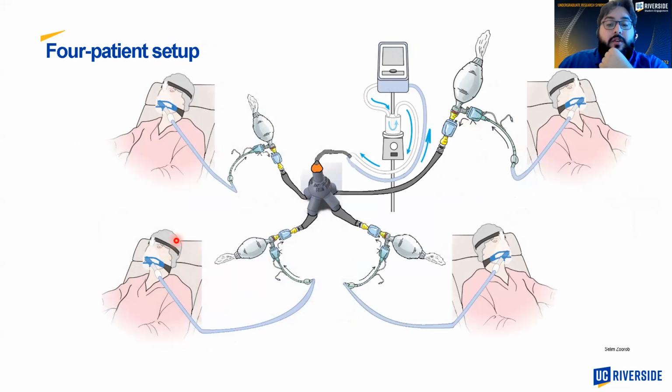And this is the final setup. This is what it should look like in case we need to hook up 4 patients into one medical ventilator. As you can see, this is the 4-way splitter I designed, and each patient has its own double filter system, to regulate the O2 saturation levels, the airflow, and to make sure that the air is filtered.